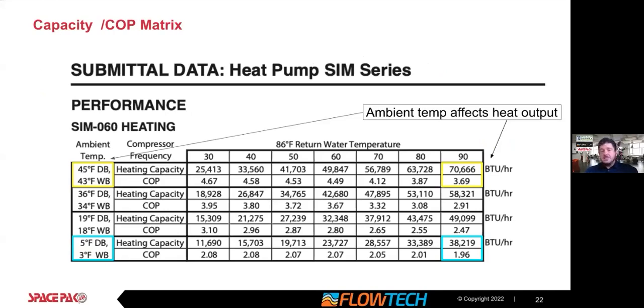This is how you design these systems and some considerations. Unlike a natural gas product where you're always getting the same BTU output, mostly, though elevation might affect that, if you have a 100,000 BTU boiler, it's going to give you that. Heat pumps are different, and it's very important to understand that this left column here is ambient temperature, and that will be impacting the capacity of the unit as well as supply water temperature. This chart assumes an 86-degree return water temperature. So when you're sizing these units, understand what your local conditions are for your design day, the average coldest day of the year. If you're designing around 45 degrees, you'll be getting roughly 70,666 BTU. Likewise, if it's a cold climate and you're designing around 5 degrees, your BTU output will be reduced.